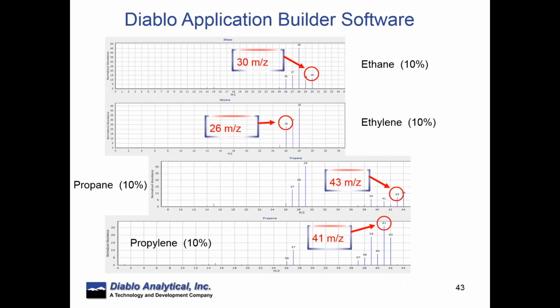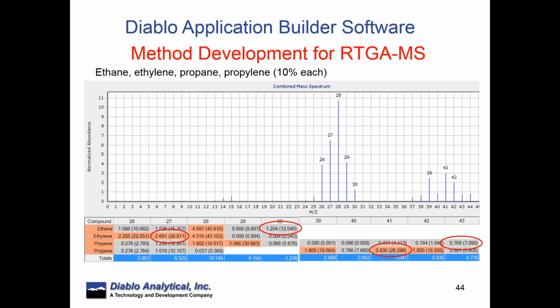Here I show another example for ethane, ethylene, propane, and propylene. And the software picks particular ions here. You can override that and choose a different one. And then from that, we're going to now make the method. And that would be showing 10% each of those components, ethane, ethylene, propane, and propylene, again with what the level of expected overlap, if any, would be between different components at a particular mass to charge ratio.